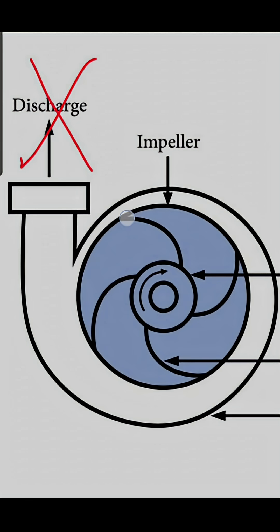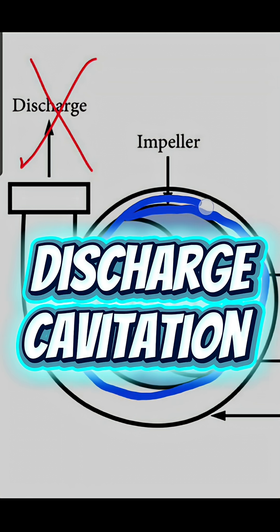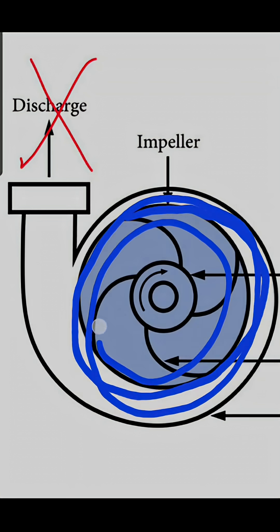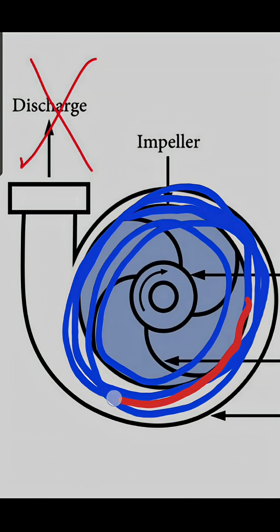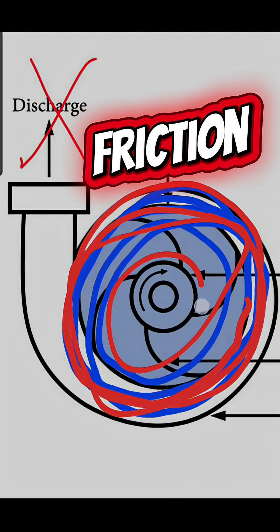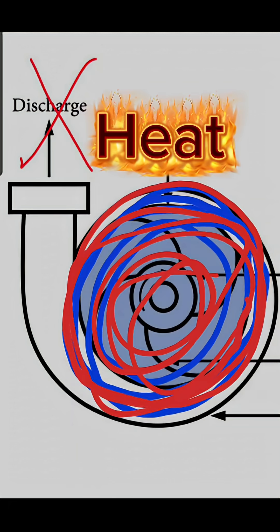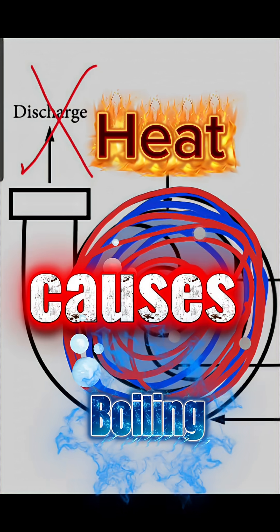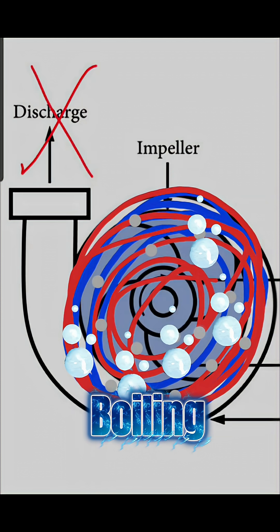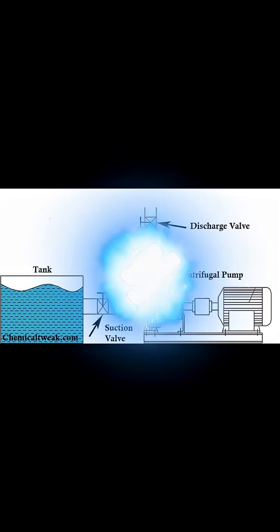Well, it depends on if it's suction cavitation or discharge cavitation. With discharge cavitation, if flow through your pump is restricted due to something happening downstream or the discharge head pressure is too high, the liquid is stuck inside the pump casing while the impeller spins thousands of RPMs. This causes friction. Friction equals heat. Heat causes boiling. So the vapor bubbles are actually boiled, processed liquid. The lack of flow causes friction, which causes the liquid to boil and results in cavitation.